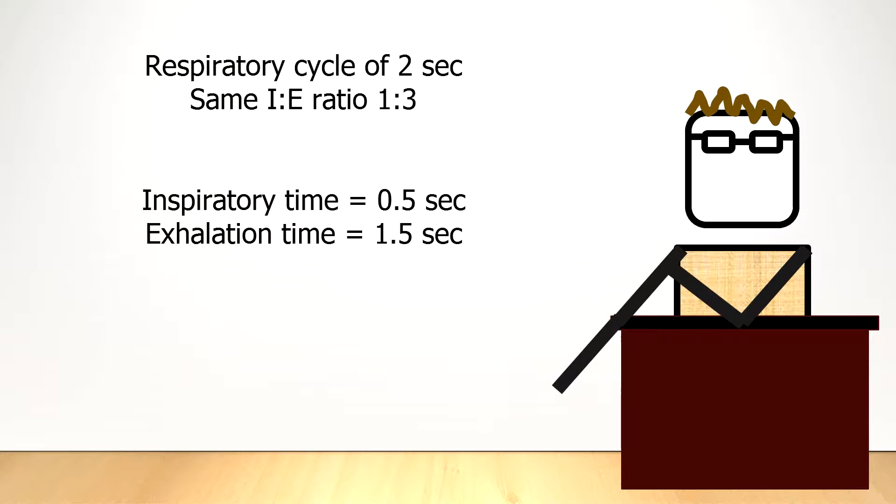If you change the total respiratory cycle from 4 seconds to 2 seconds, but maintain the same ratio, then the TI becomes 0.5, and the exhalation time is 1.5 seconds. The ratio remains the same, however.